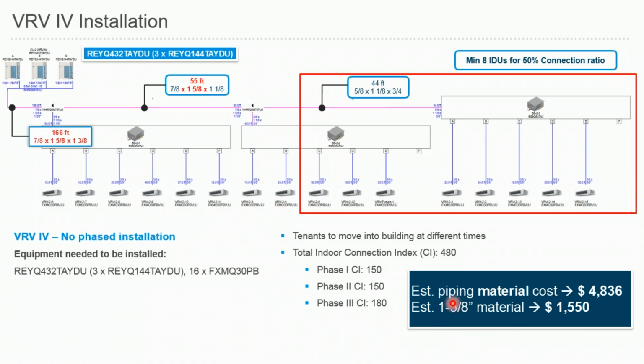So over here, the estimated piping material cost is close to $5,000. And if you look at your main line, you're using the standard pipe sizes that we publish in our manuals. If you look at the suction lines, 1-5/8" diameter pipe size. So close to $1,600 of cost is coming from that 1-5/8" main line.